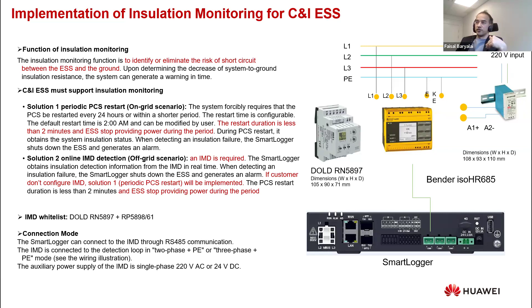For the on-grid system, the PCS automatically runs its isolation resistance test every 24 hours, for 1 to 2 minutes. But for off-grid, it's important to have an IMD.